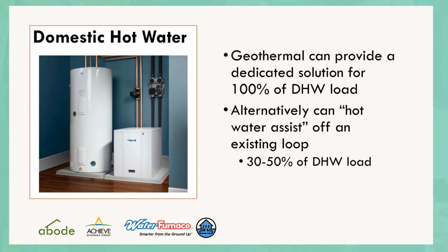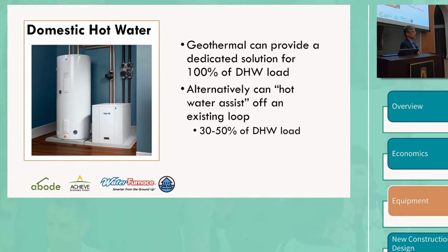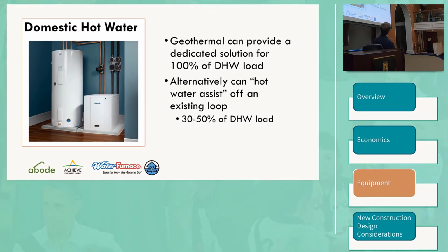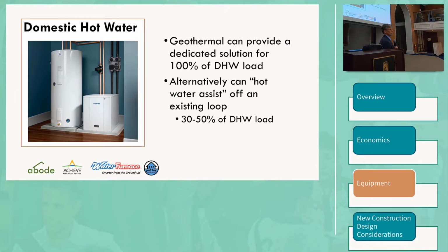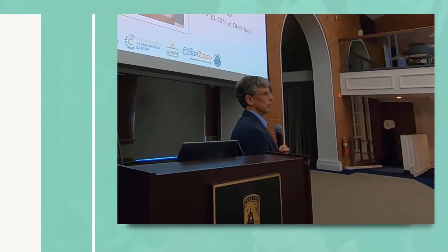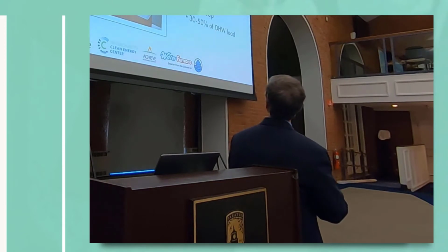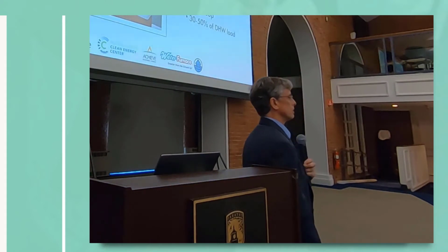Domestic hot water. Unlike some of the other technologies, ground source can help with domestic hot water. There are two approaches. The simplest but most expensive is to have a separate ground source heat pump that's dedicated to providing 100% of the domestic hot water. Or if you have a hydronic load like radiant flooring, size the heat pump a little bit larger and have it automatically switch between domestic hot water and the radiant floor. And that can be relatively cost effective, but putting in the pumps, controls, and heat pump just for domestic hot water can cost some money.